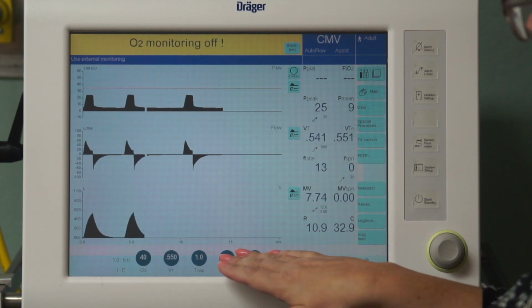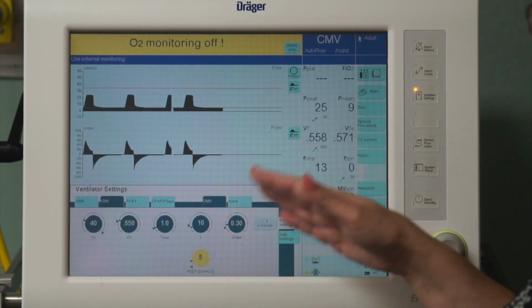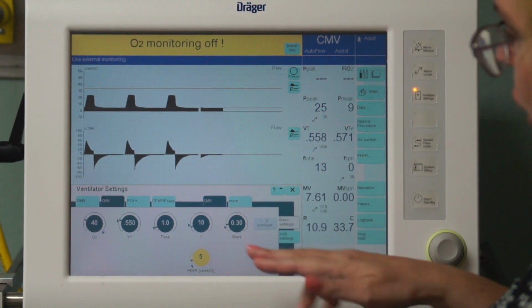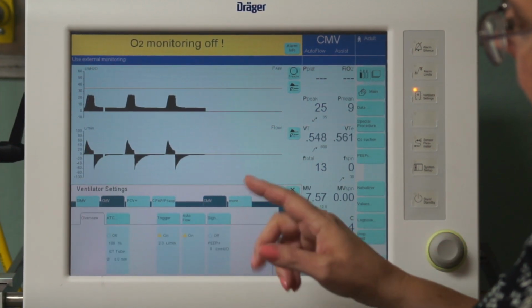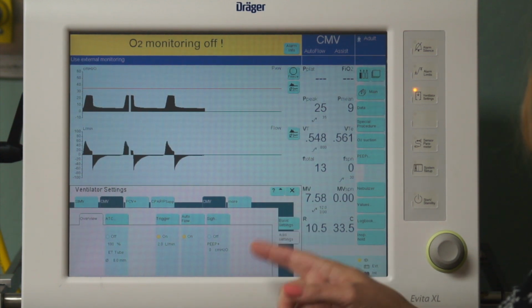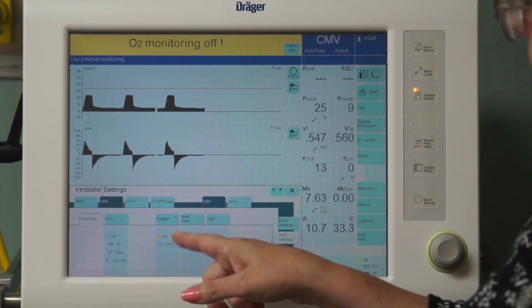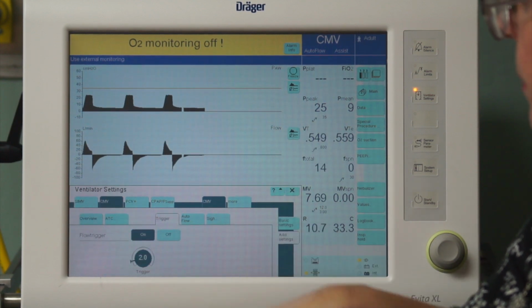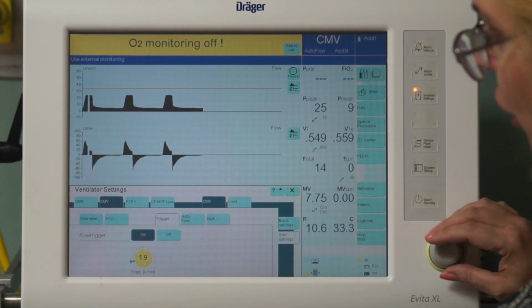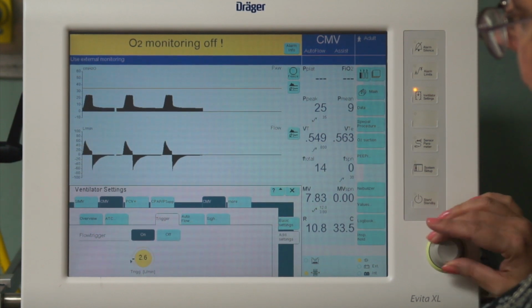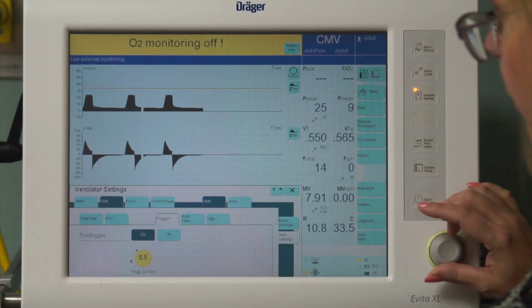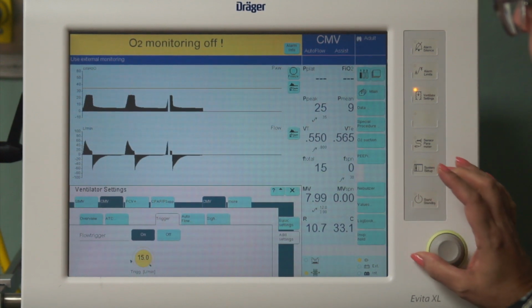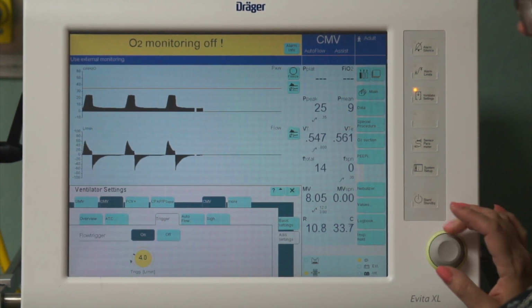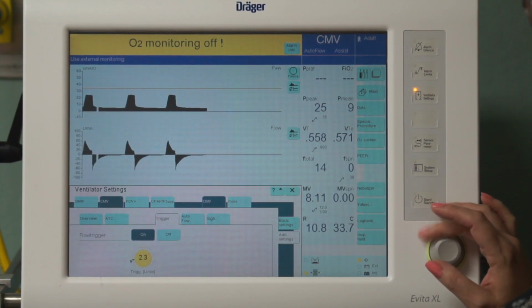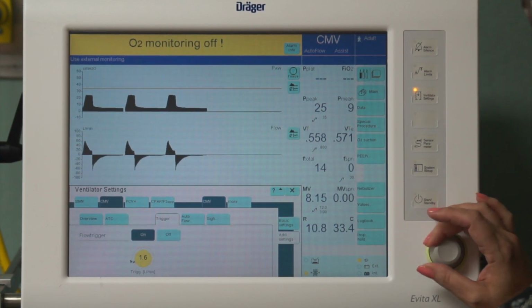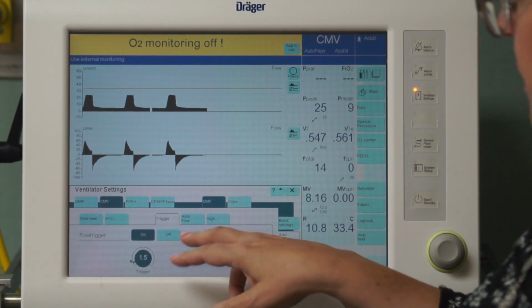Now I'm going to go back into here, and I just touched it, and the tab system came up, and I'm going to look at additional settings. Now, the additional setting we're always going to need to set is our sensitivity or our trigger, right? So I'm going to look at my trigger, and I notice I'm in liters per minute here, and as I go through, this is my flow trigger. So these are all in liters per minute. So I'm going to choose something reasonable, and I'm going to set that flow trigger.